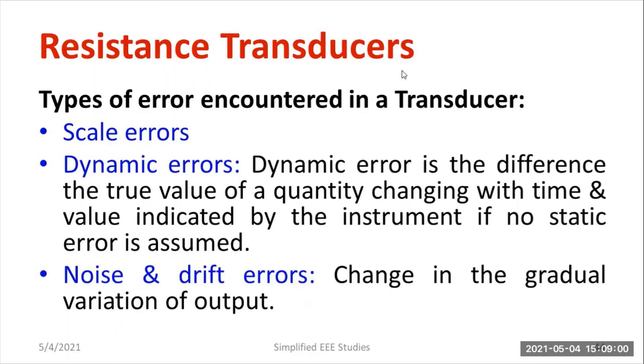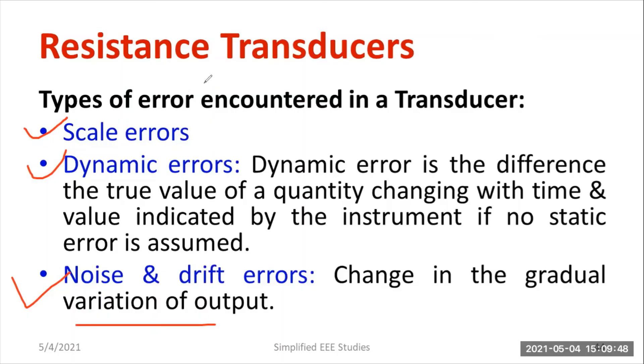The major errors encountered in this kind of transducer are: first, scale errors because the scale is non-uniform, which affects accuracy. Second, dynamic errors — the difference between the true value of a quantity changing with respect to time and the value indicated by the instrument when no static error is assumed. Third, noise and drift errors, occurring mainly due to gradual variation in the output. These errors are most common in resistance transducers, making them unsuitable where high accuracy is required.